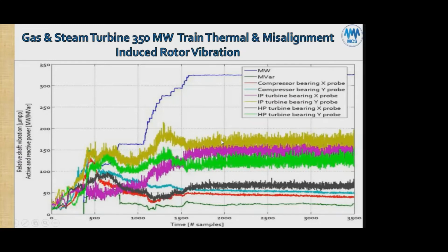If you look at the IP rotor vibration, we're talking about continuous operation at 175 microns. It's too high. Typically, the max allowed to be considered smooth at this size machine would be 100 microns. So they're quite above. Is there a problem? The answer is yes. What's the solution? Trends like this are a very important studying tool. The other is the vibrational XY orbits at each bearing. Even casing vibration is good to have. Casing vibration in the vertical, horizontal and axial directions is very helpful for judging.